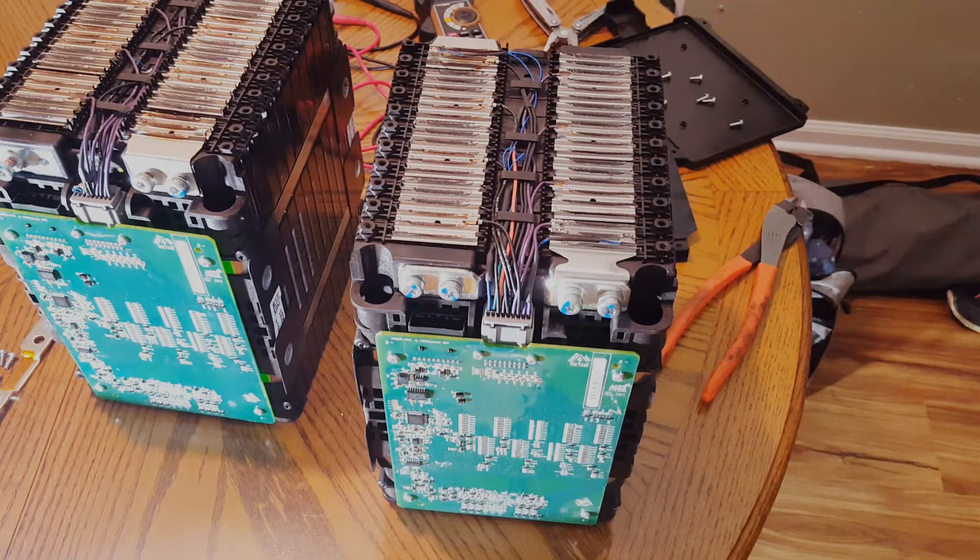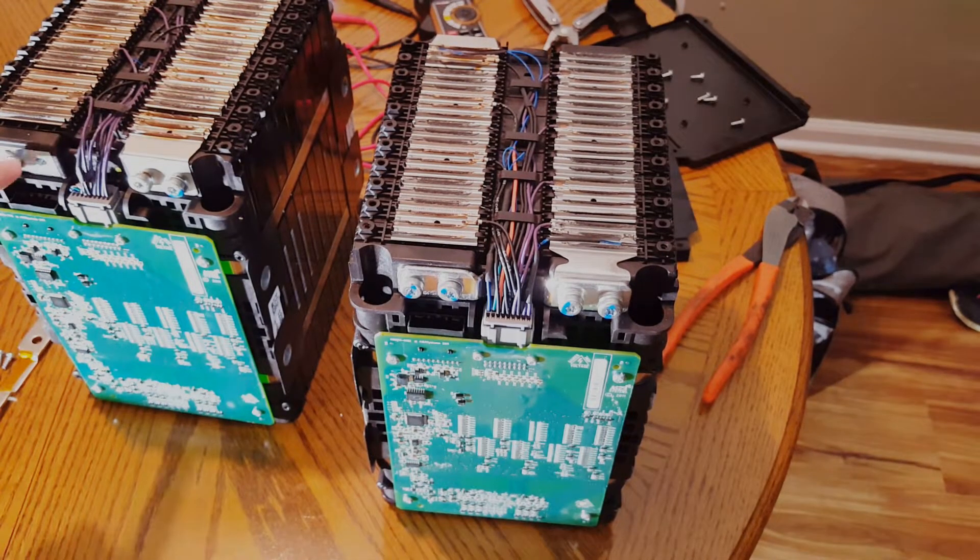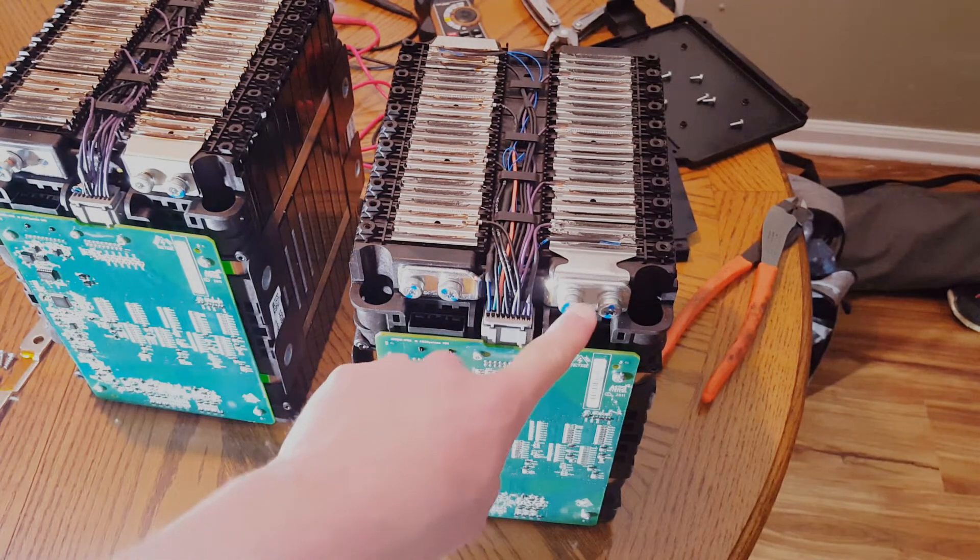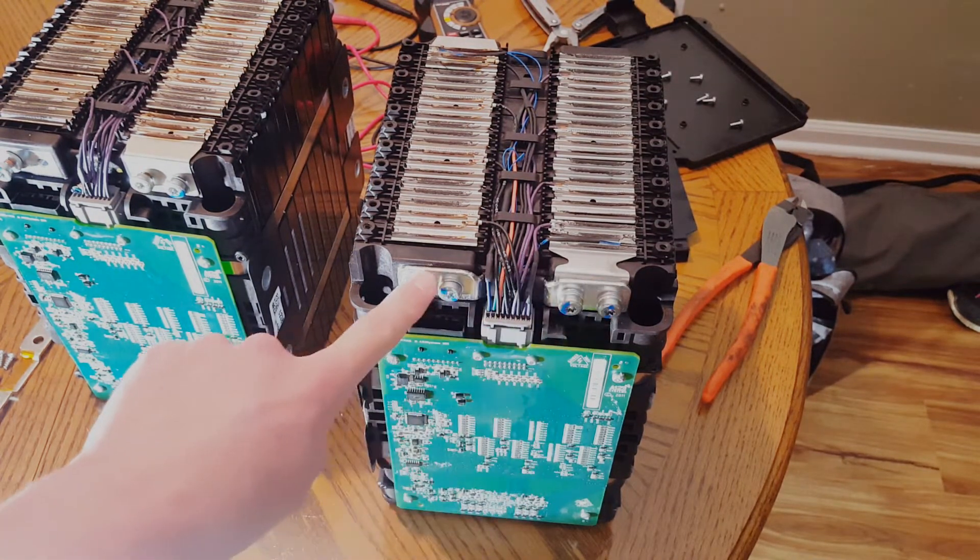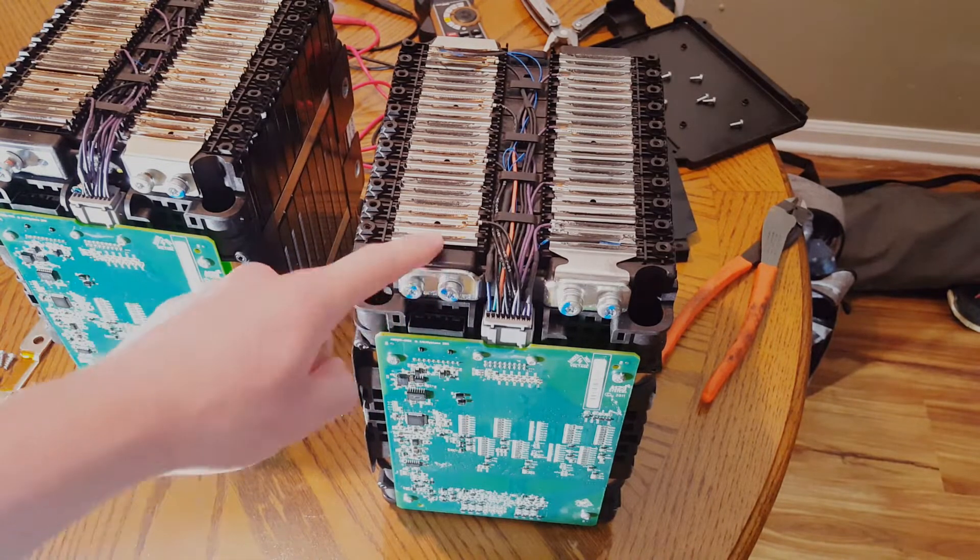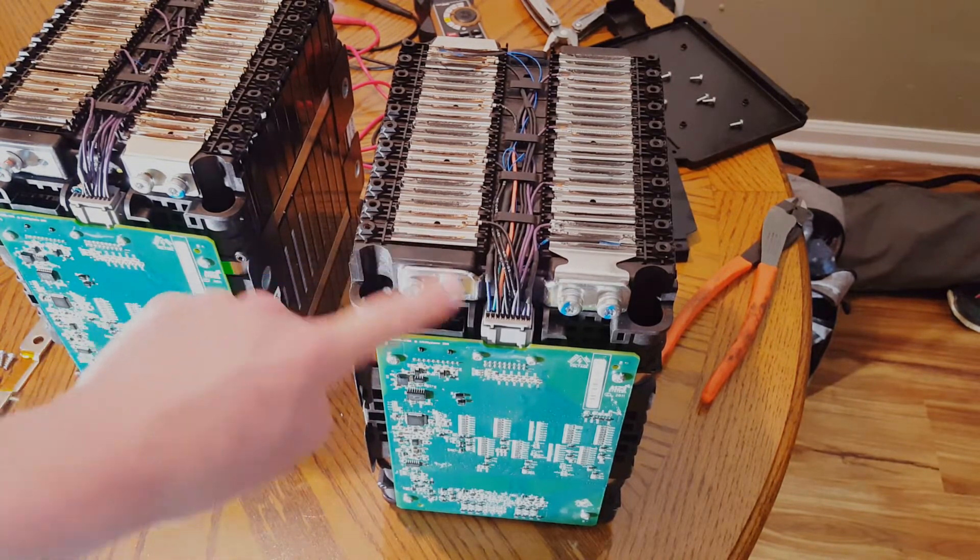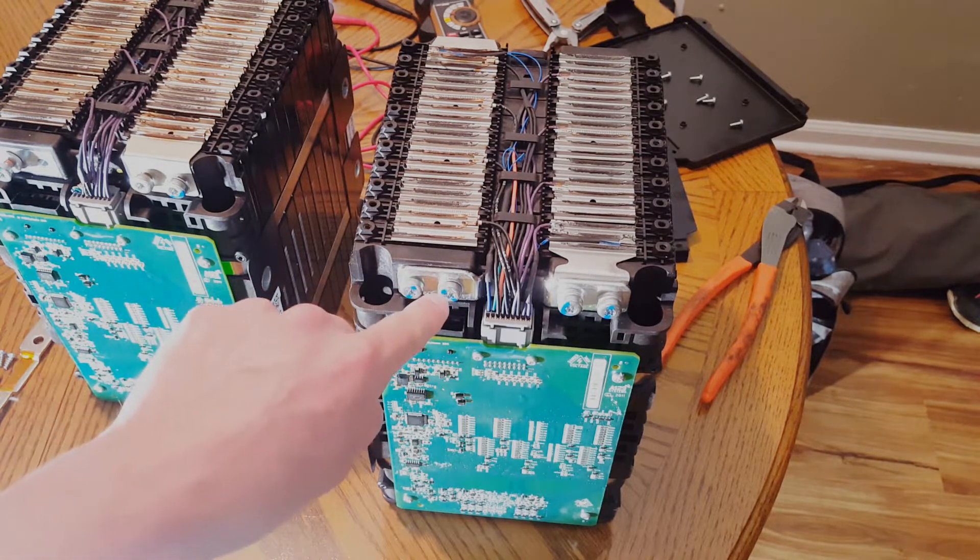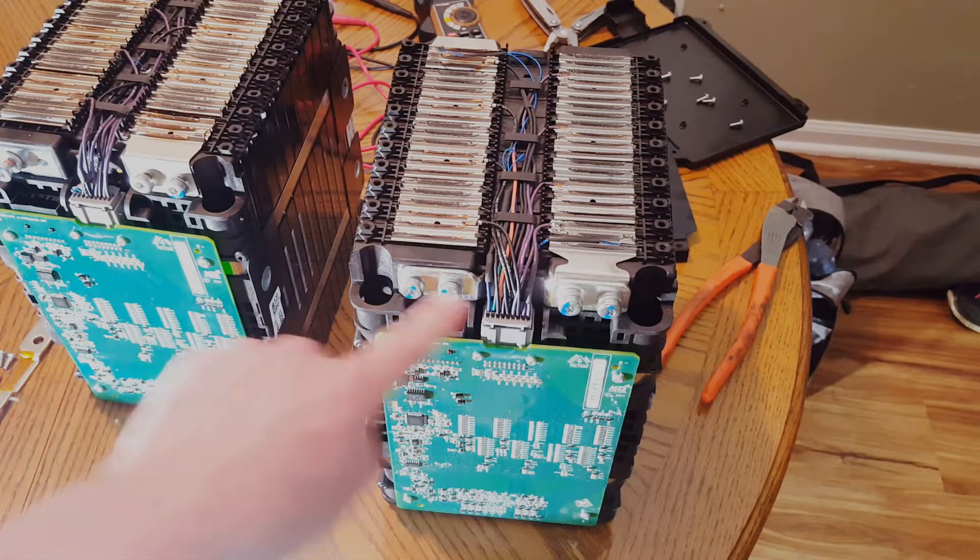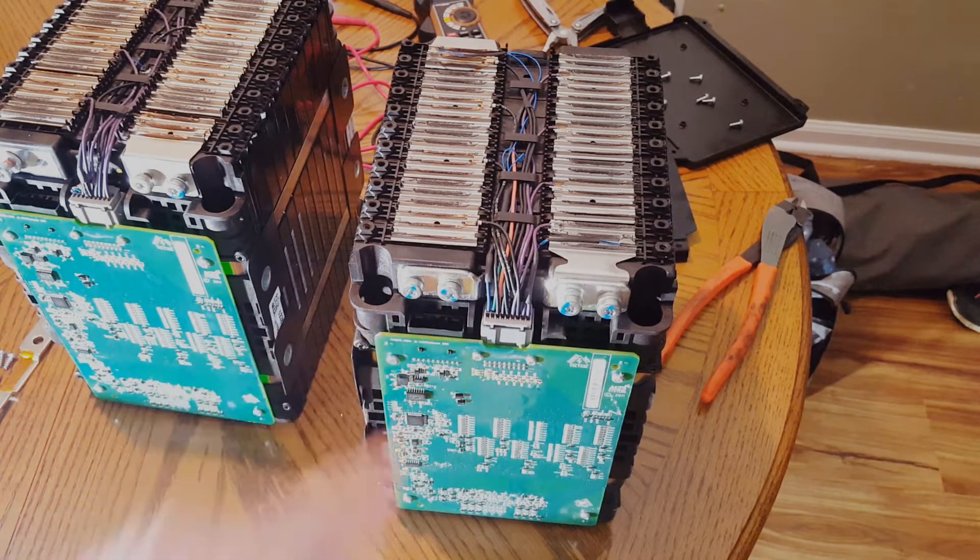One more thing before I forget, I said that this was the main negative and this was a dummy terminal. The same thing applies for all of the positive terminal. So this is your main positive. And this bus bar was on here and you can see that there's nothing here wrapping around connecting to anything up top. So this terminal is dead, but alive right now. It's live right now based on this bus bar running back here.